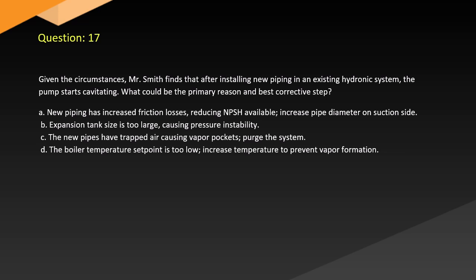Question 17. Given the circumstances, Mr. Smith finds that after installing new piping in an existing hydronic system, the pump starts cavitating. What could be the primary reason and best corrective step? A. New piping has increased friction losses, reducing NPSH available. Increase pipe diameter on suction side. B. Expansion tank size is too large, causing pressure instability. C. The new pipes have trapped air, causing vapor pockets. Purge the system. D. The boiler temperature set point is too low. Increase temperature to prevent vapor formation.